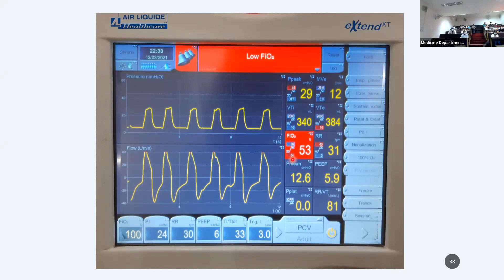So in case you have a suspected ventilator issue, check the tubings and connections of the ventilator. In this case, we found that the connection of oxygen tubing to the wall socket was loose, as a result of which adequate FiO2 was not being delivered. Ensure that the compressor is on. If the compressor is not on, the set variable will be, for example, FiO2 of 30%, but the FiO2 being delivered will be 100% because the compressor is not on, so no air is being mixed.